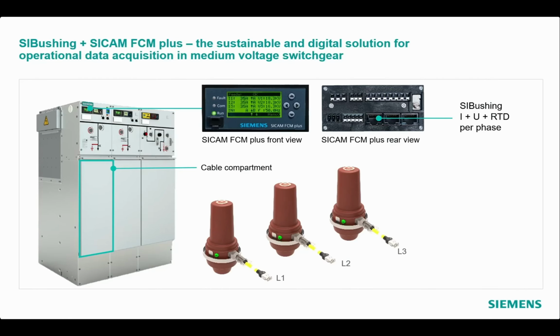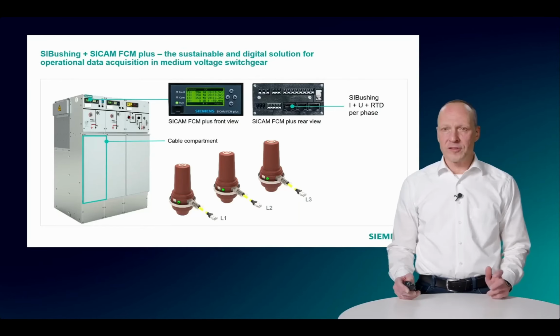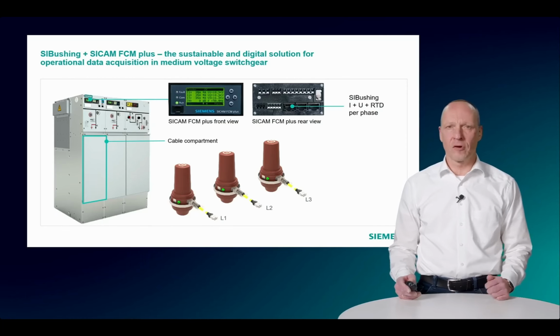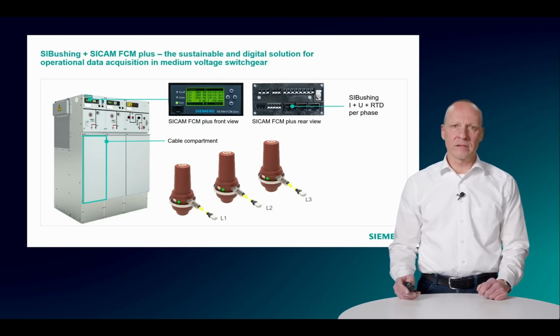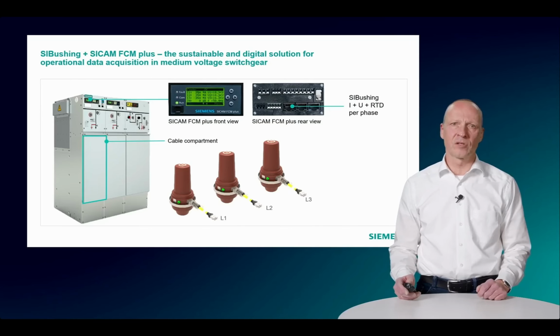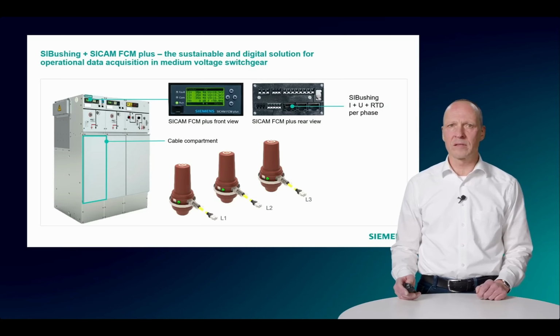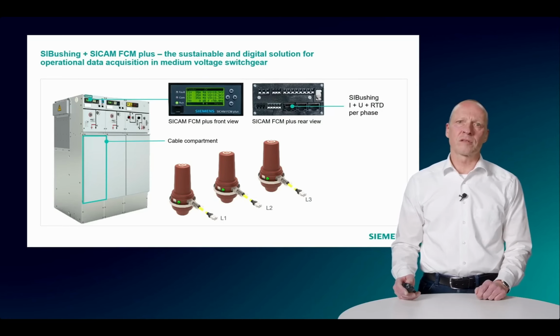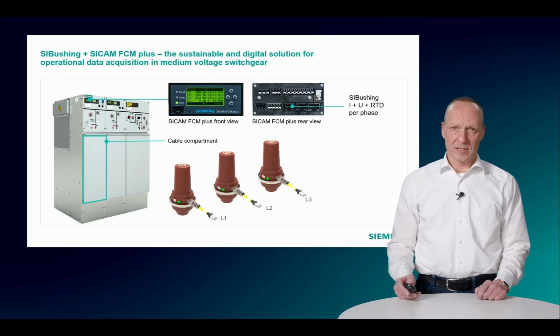Digital secondary substations are using multifunctional short circuit and earth fault directional indicators like our SICAM FCM plus, featuring directional sensing and protective algorithms. Together with the integrated LPITs into the SIBushing, it can indicate the fault and its direction. Furthermore, it provides up-to-date measured values of current, voltage, frequency, cosinus phi phase angle, as well as active and reactive power. These values are digitized in the device and provided via an integrated Modbus RTU interface for further use to a gateway in the substation. The connection of the SIBushing to the SICAM FCM plus is realized with standard RJ45 connectors on the backside.